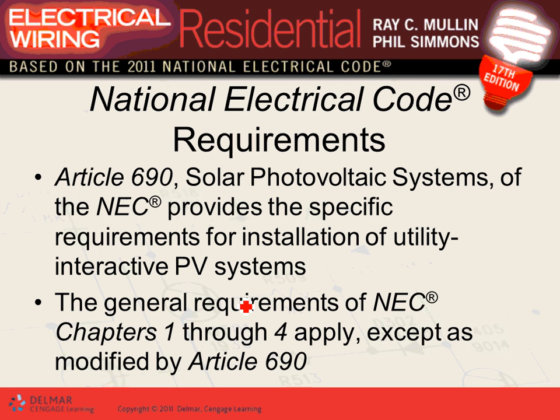Okay, Article 690, guys, talks a lot about the regulations. We'll talk about this one for solar photovoltaic system, the requirement. Now, I want to remind you guys, Chapter 1 through Chapter 4 also covers solar photovoltaic system. For example, conductors need overcurrent protection device. That's in Article 240. For example, installing PVC conduit or EMT conduit. That's in Chapter 3. You have to adhere to the rules of Chapter 3.